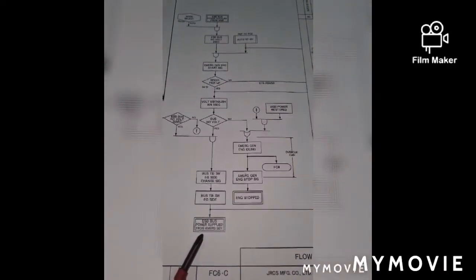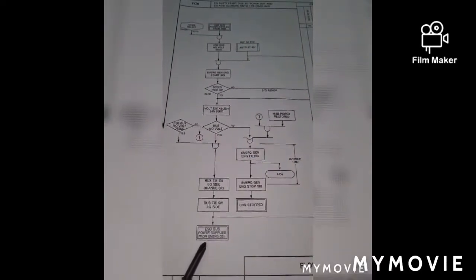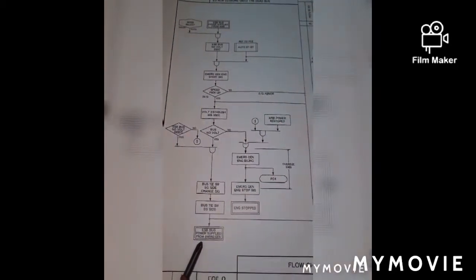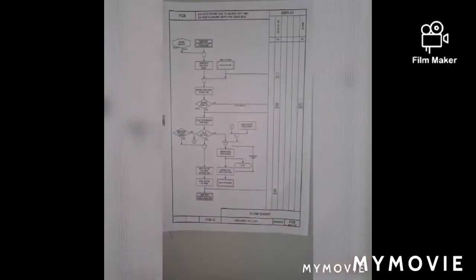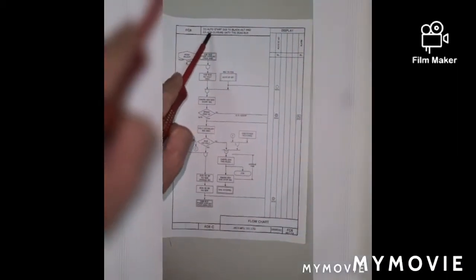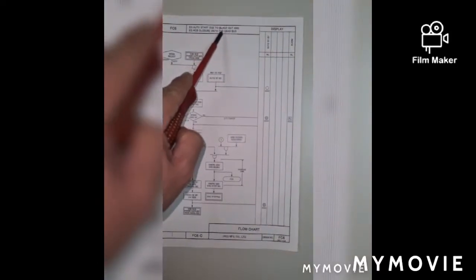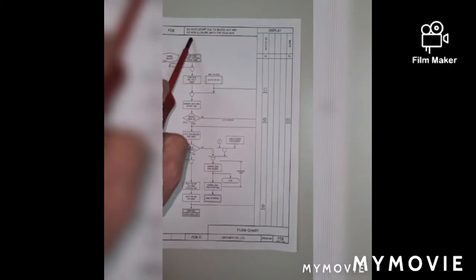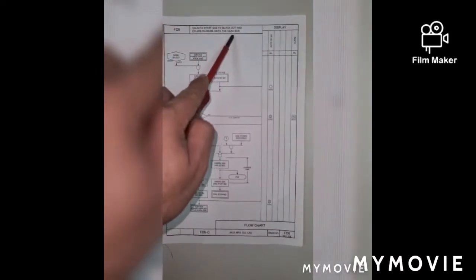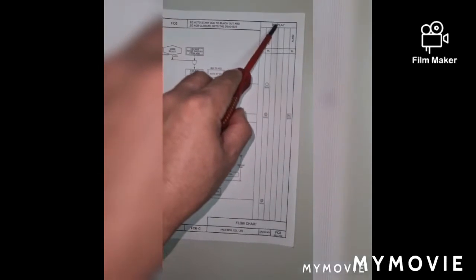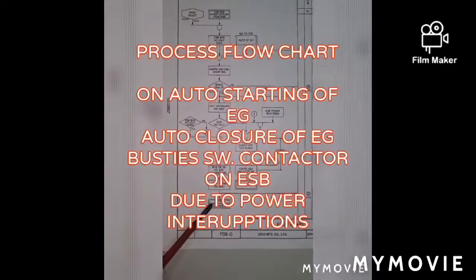Here I have a flowchart. This final condition states that the emergency switchboard bus bar is supplied power. How is the final condition being accomplished? To put the title, our title is Emergency Automatic Start of the Generator Due to Blackout and Emergency Generator Air Circuit Breaker Closure on the Dead Bus of the Emergency Switchboard Bus Bar. From here, you can see the display and how it is started.